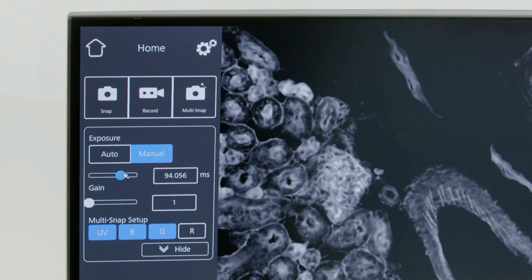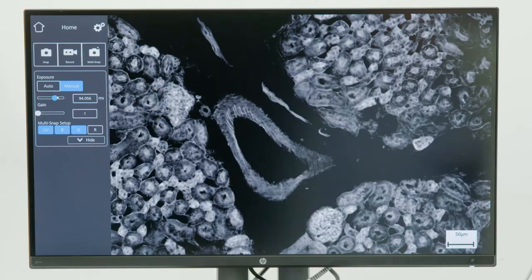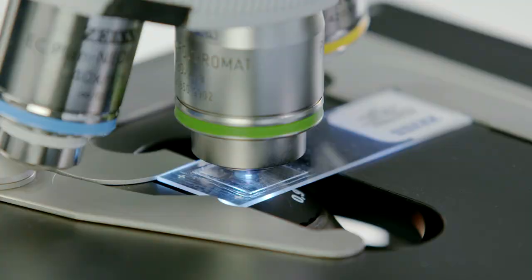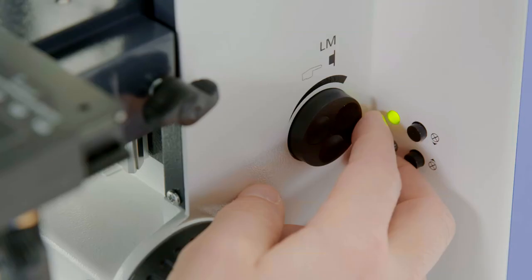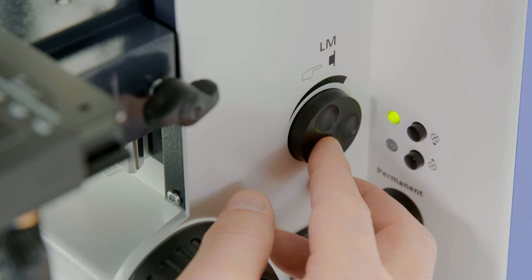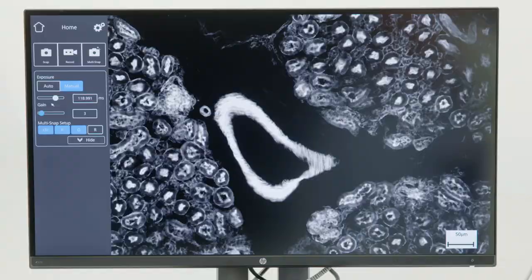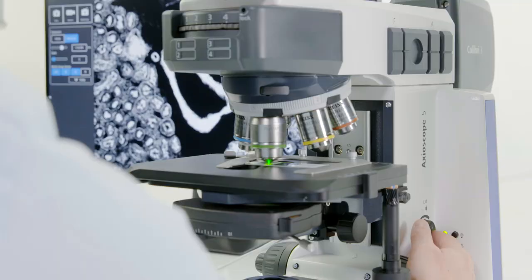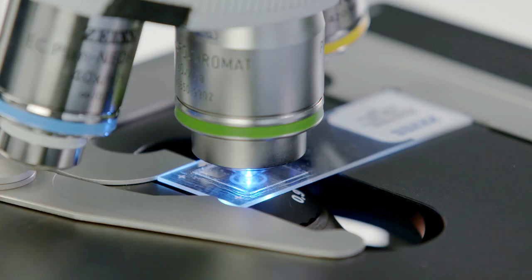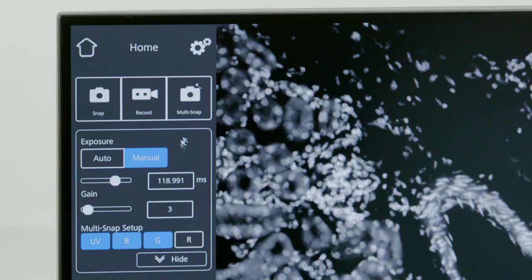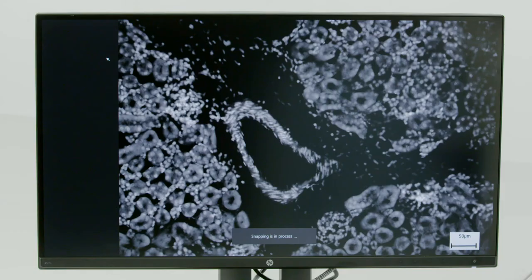Toggle to the blue LED and adapt the LED intensity with the light intensity button on the microscope so that the fluorescent signal on the monitor looks good and is not overexposed. Toggle to the green LED and do the same. Press snap. Your system takes over.